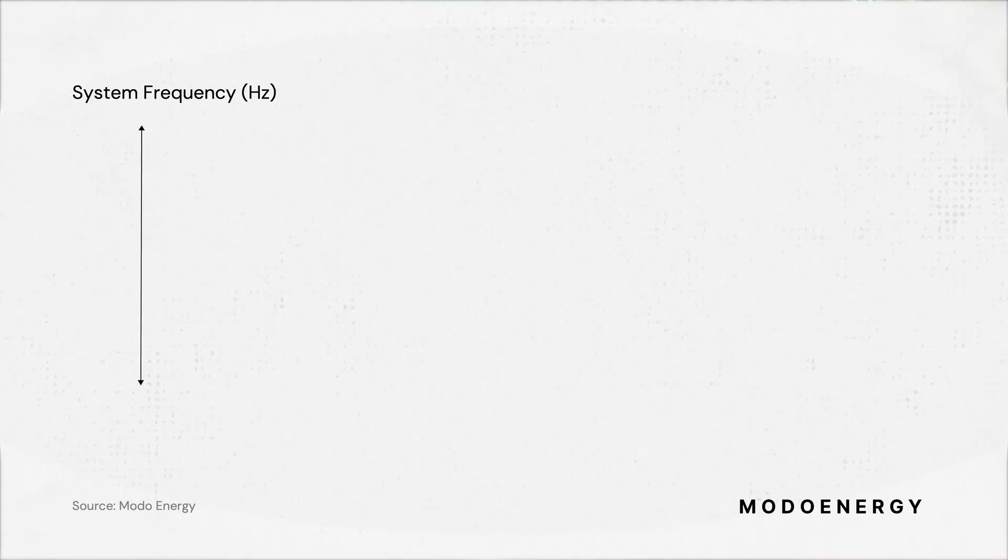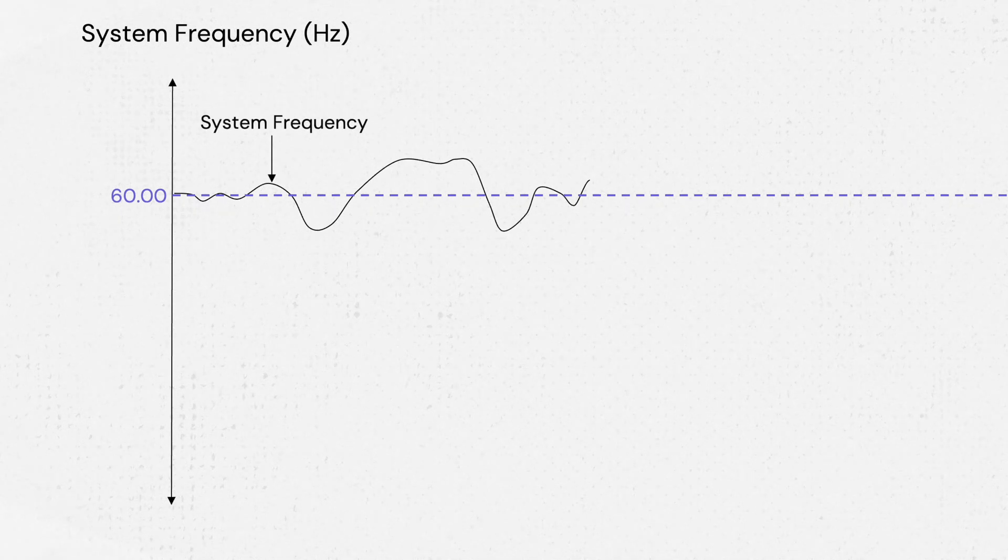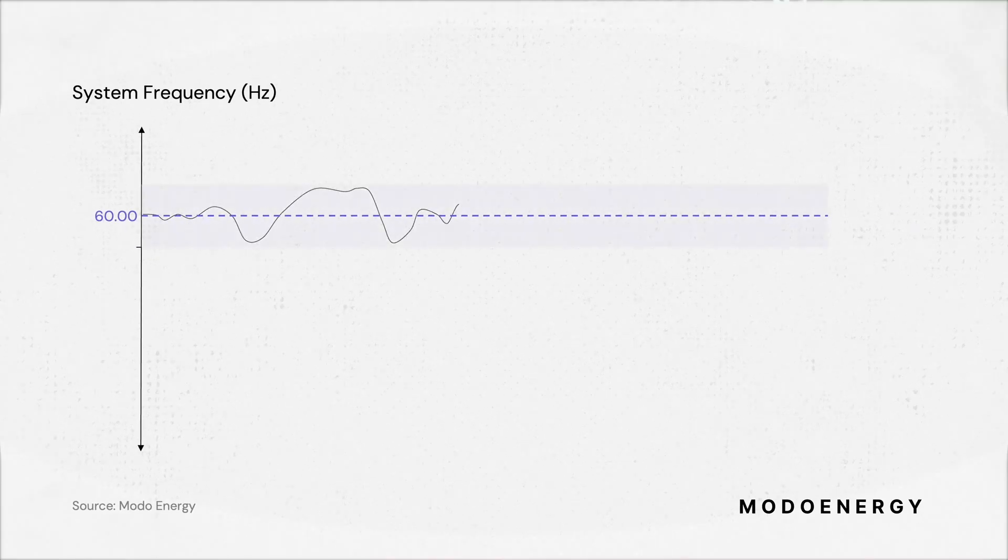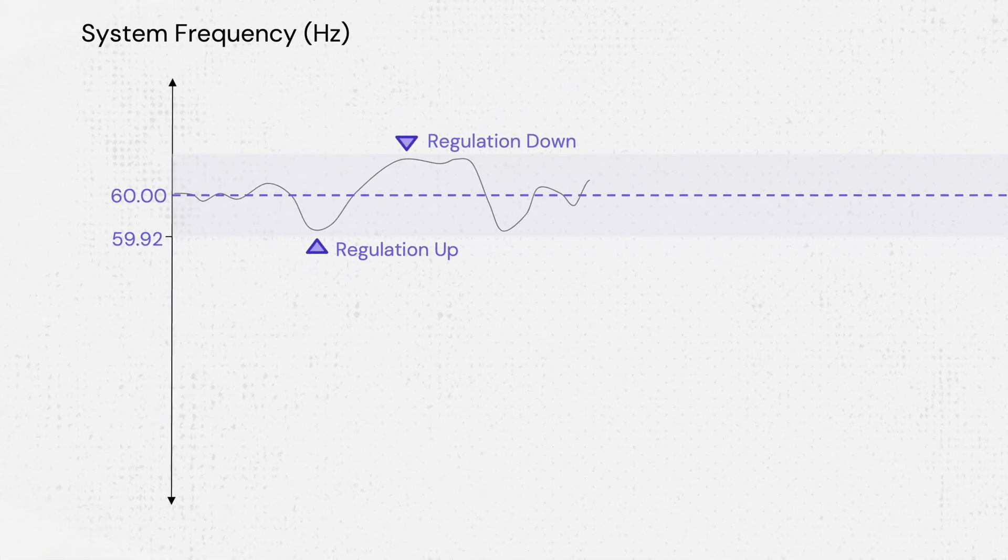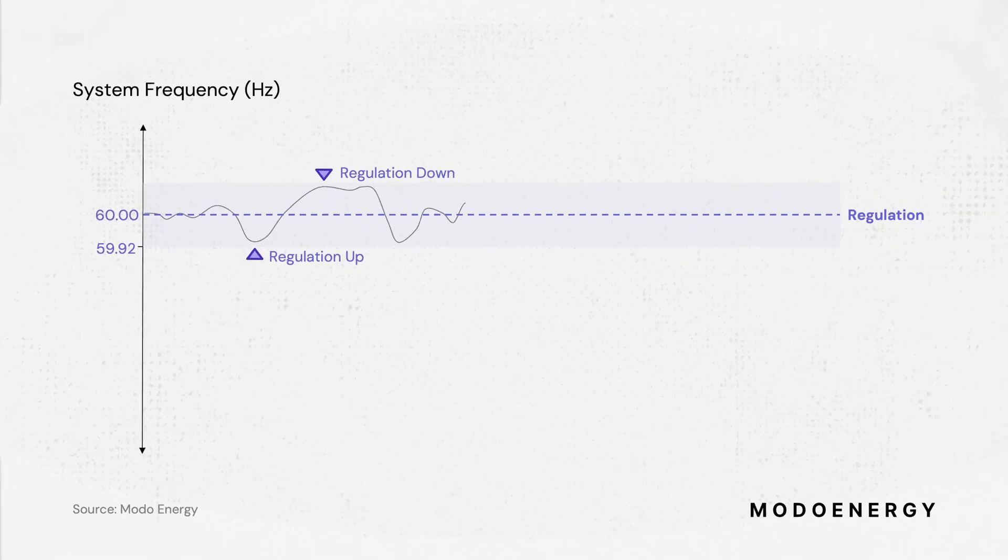In this graph, we can see system frequency fluctuating at around 60 hertz. This is due to small changes in supply and demand that occur continuously throughout the day. The regulation up and down services correct these fluctuations and keep frequency in check. These services are constantly running.